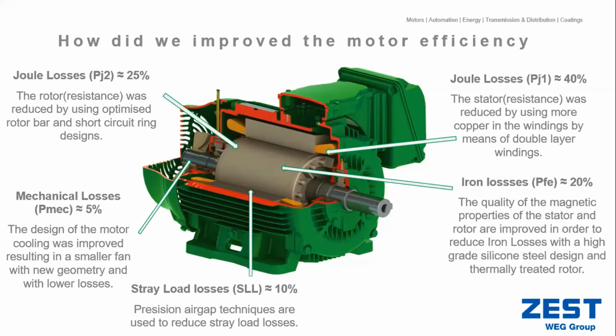The last factor is the Joule losses in the rotor. We look at optimizing the shape and design of the actual rotor bars and the short circuit rings that sit at the end of the rotor.